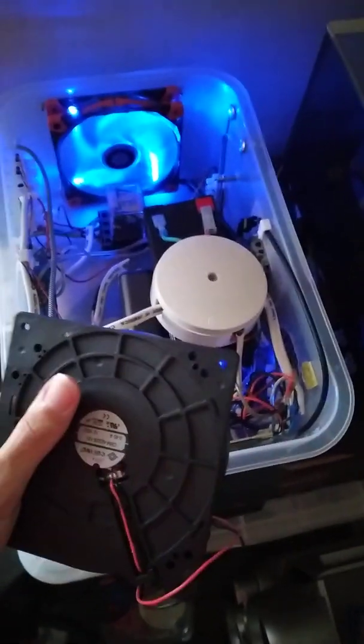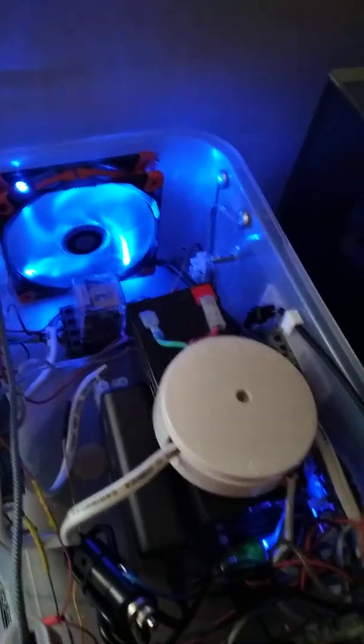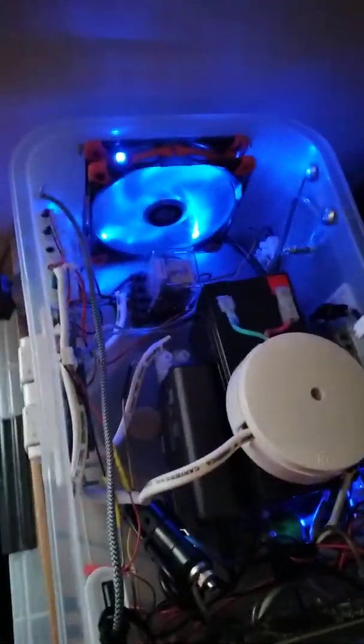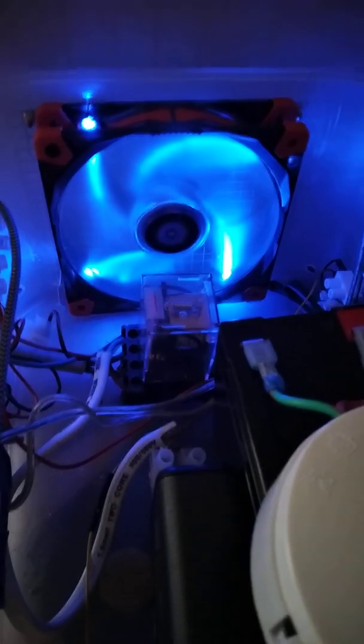But the thing is the axial fan is a low pressure fan. It's a low static pressure fan. It's designed for use without any obstructions. So if you're trying to cool any constrained areas, like for example some rack servers, where there's hardly any space for air to pass through, or you're trying to draw air through a HEPA filter, this fan is not going to do that job because it's just not intended for that.